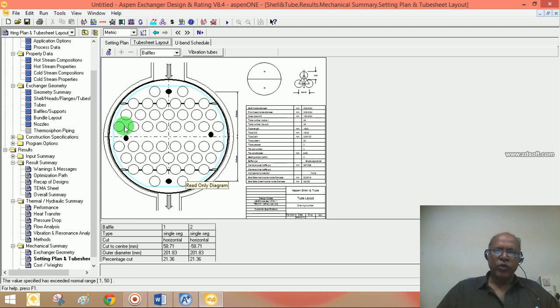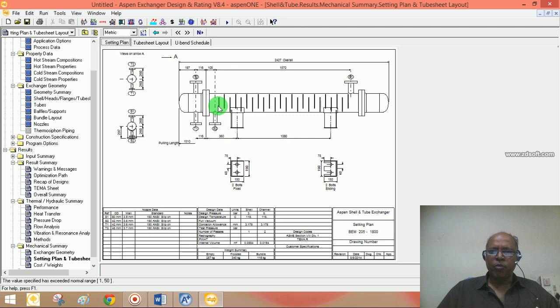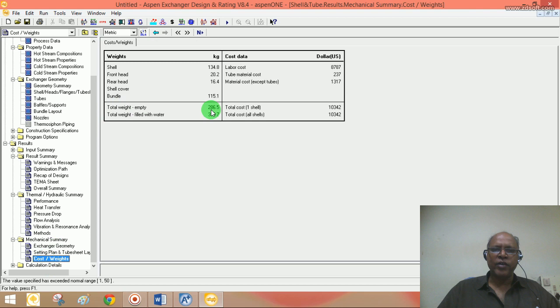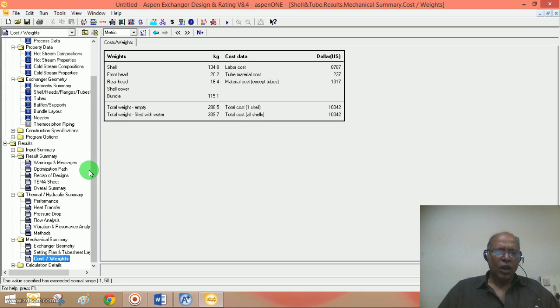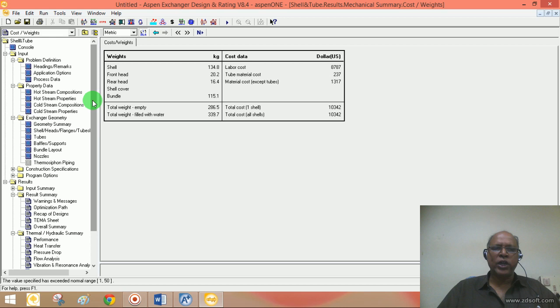Since a triangular pitch with 1-2 pass configuration is used, you can see half the tubes on one side and the other half on the other side. The number of baffles, as per the spacing and baffle cut, are shown in drawing form — these details can be sent to a fabricator. The total weight of the heat exchanger when empty is about 268.5 kg, when filled with water about 339.7 kg, and this is the total cost. Such zonal property calculations cannot be done manually as easily.